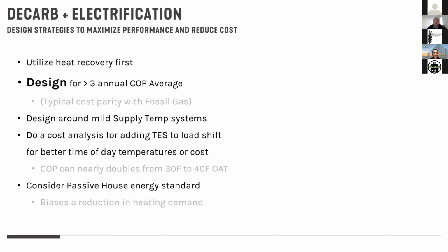You want to do a cost analysis for adding thermal energy storage, especially on the performance side, but make sure you're taking advantage of it for load shifting into beneficial temperature hours, better daytime hours when the temperature is higher. The COP can almost double going from a cold temperature to slightly warmer. So pay attention to it.